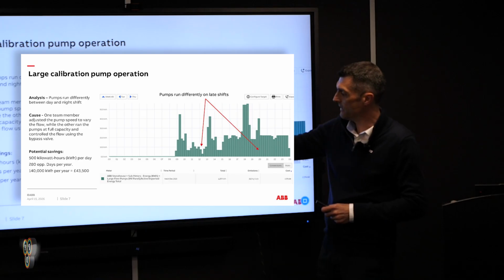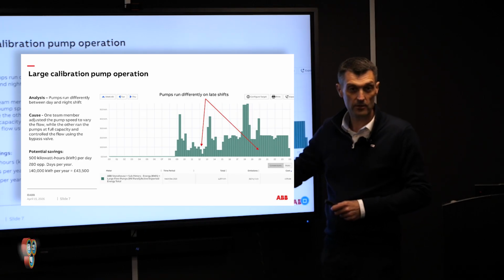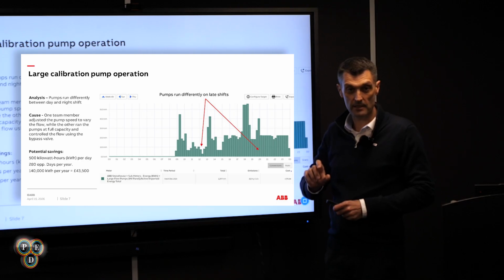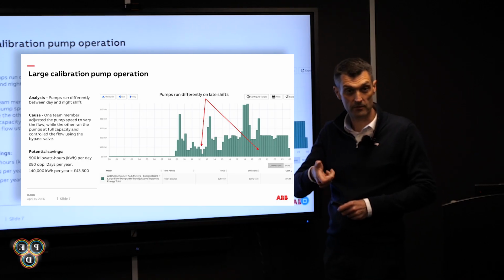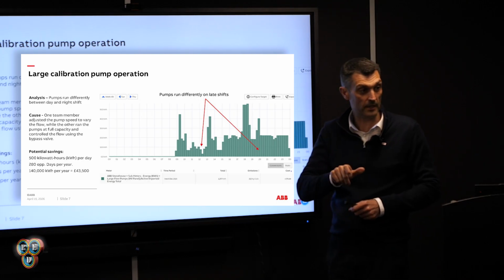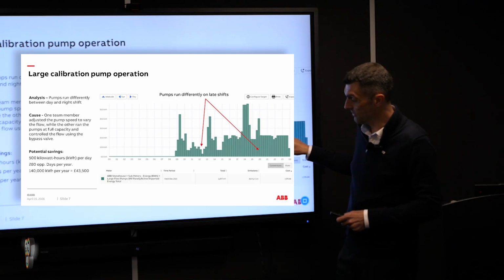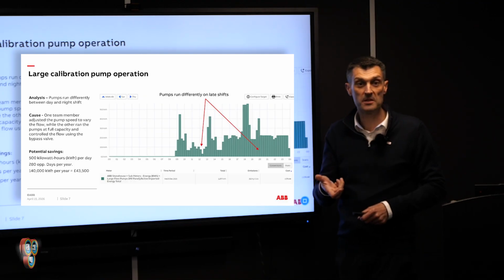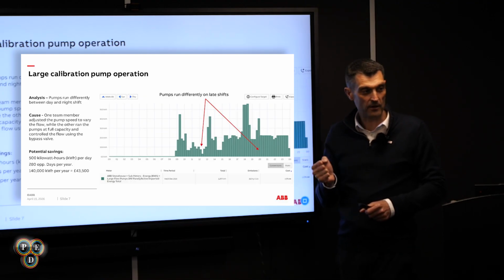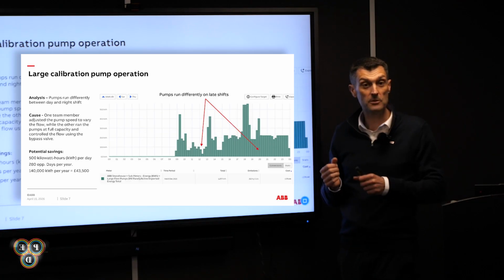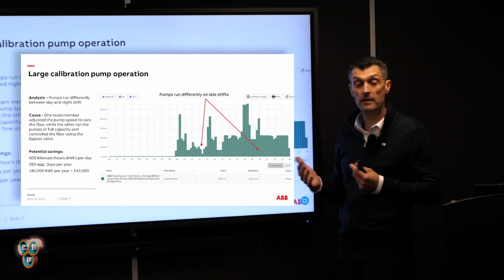What's going on here is the day shift operator uses the machinery as intended - it's a variable speed drive, so he just changes the amount of power needed to achieve the result. The night shift operator just ran it at 100% and used a bypass valve to create the desired flow - doing it mechanically, apparently because that's how he was trained.